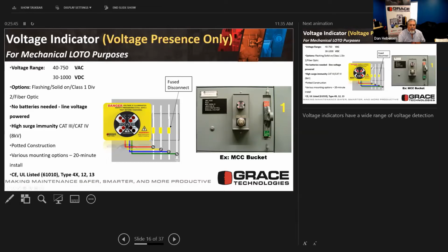So going back again, typical environment, 480, you're going to have three lights flashing and seeing that the energy's there. These are high surge immunity. They're Cat 3 and Cat 4 rated. They are a fully potted construction. There's a lot of different mounting options. It typically takes about 20 minutes to install these types of devices, and they are UL listed 61010 as we had talked about.